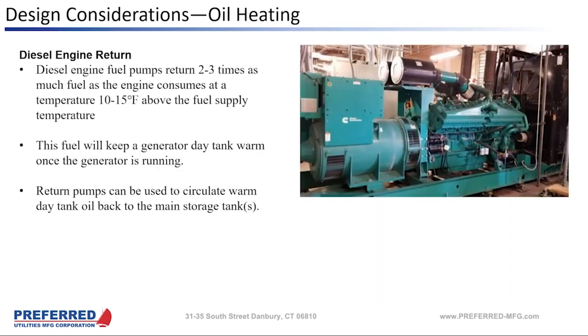The thing about diesel engines is they pull fuel out of your fuel supply header, but then they return 2 to 3 times as much fuel as the engine consumes. And that returned oil is used for cooling the fuel rails on the diesel engine. So that oil comes back at 10 to 15 degrees higher than the supply temperature, depending on the size of the engine. And this warm oil will keep a day tank warm once the generator is running.